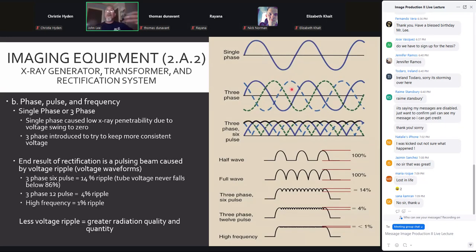Now, taking those 3 lines, three positives, 3 negatives per cycle, flip them up, and now you have doubled it. So we've got 6 pulses per 60th of a second. Now, that causes even less of a dip in our voltage. So if we look at 3-phase 6 pulse, it's measured out as 14%, which means that the kinetic energy that we give to our electrons flowing in our tube during the exposure only drops down 14% from peak. So at 100 kV setting, we're only going to drop down to 86 kV, whereas full wave single phase, we dropped all the way down back to 0.